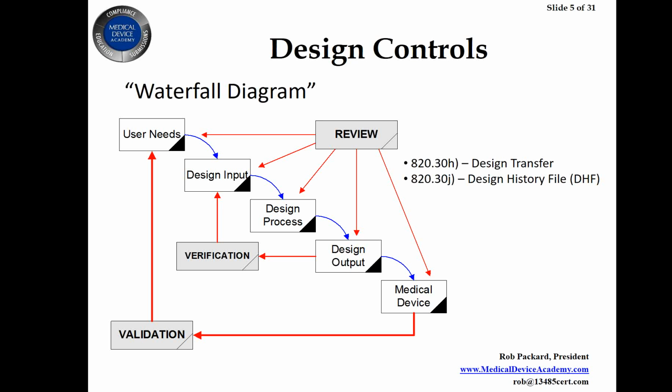Health Canada took an active role in the development of the ISO 13485 standard that was written at the same time by the same committee, or some of the same people that worked on the QSR, specifically Kim Troutman. And so you'll see this diagram links up very nicely whether you're in ISO 13485 or you're in the QSR. And I always had on this particular slide these 2 bullets over to the right. These are the 2 areas that weren't covered in the ISO standard, but now they are. They've added these 2 sections to the ISO 13485 2016 version, and so you have those included now, and now it's 10 sections instead of 7.